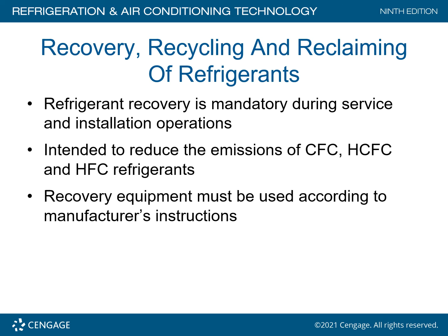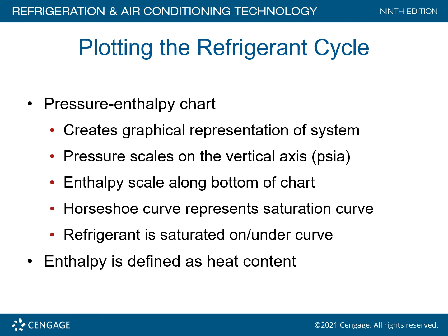Plotting the refrigerant cycle. A pressure enthalpy chart creates a graphical presentation of the system. The pressure scales on a vertical axis, which will be illustrated as PSIA, which is your pressure absolute, and the enthalpy scale is along the bottom of the chart. Remember, this is going to be your sensible heat plus your latent heat, which you cannot measure. The horseshoe curve represents the saturation curve. Refrigerant is saturated under the curve. Enthalpy is defined as heat content.